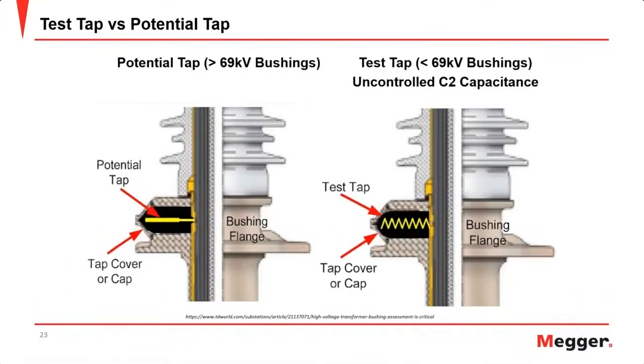So when you measure the C2 capacitance for a bushing with a potential tap, you will see greater consistency between the uninstalled and the installed capacitance for C2. For these types of bushings, we call this a controlled C2 capacitance. So it is very important to know, whether you're testing low voltage or high voltage bushings, that the tap construction can have a significant impact on the capacitance that's measured while it's suspended before it's installed and then after it is installed.